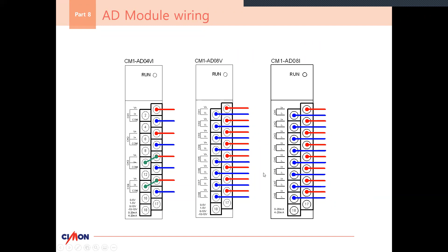A little about the setup: when you have the module connected to your PLC, inserted into your chassis or hooked up to your PLCs, Cimon software will automatically detect it. Once you're online, double left click on the module and you'll get a configuration window. Then click on the channel you want to set up—in this case, channel 2. Press setup, then go through the different parameters, such as the input type, which here is chosen as 4 to 20 milliamps.